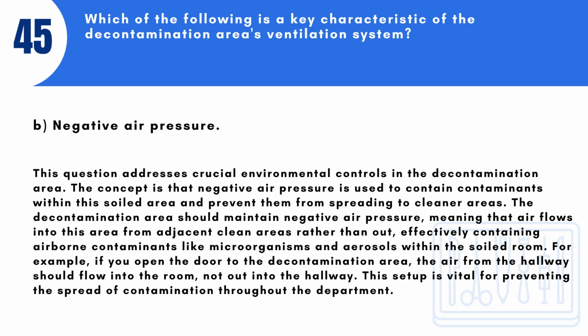This question addresses crucial environmental controls in the decontamination area. The concept is that negative air pressure is used to contain contaminants within this soiled area and prevent them from spreading to cleaner areas. The decontamination area should maintain negative air pressure, meaning that air flows into this area from adjacent clean areas rather than out, effectively containing airborne contaminants like microorganisms and aerosols within the soiled room. For example, if you open the door to the decontamination area, the air from the hallway should flow into the room, not out into the hallway. This setup is vital for preventing the spread of contamination throughout the department.